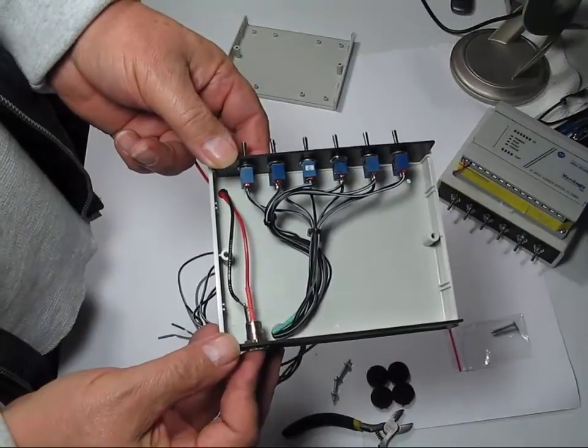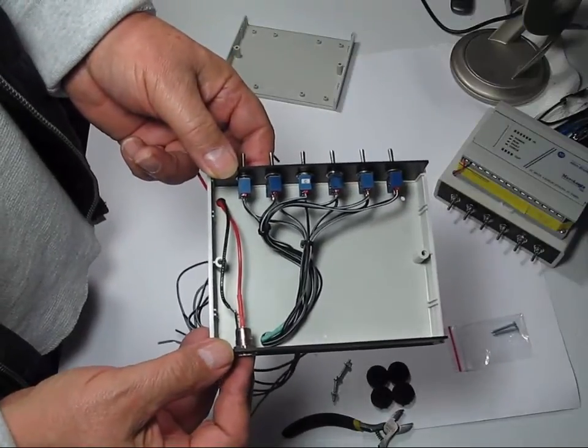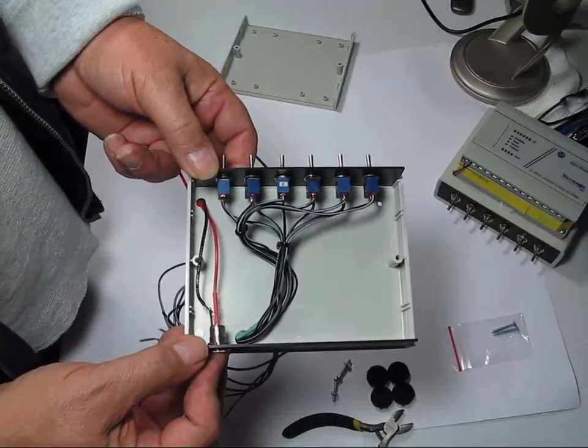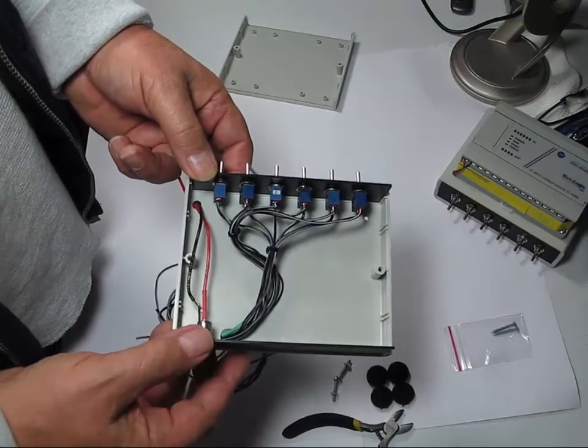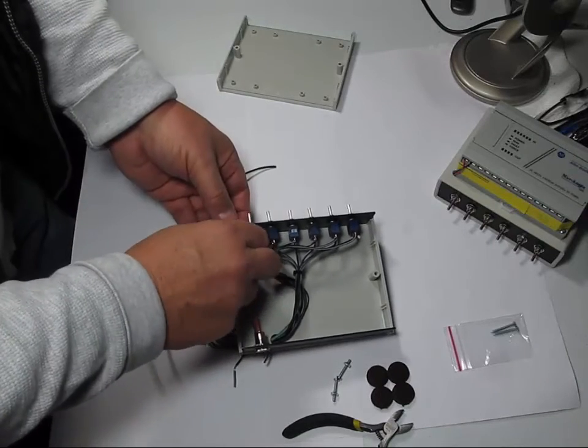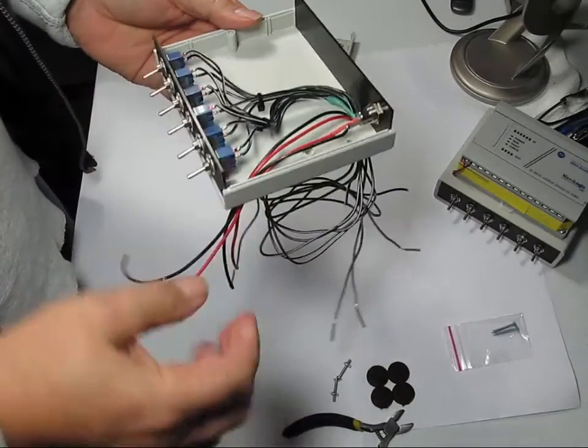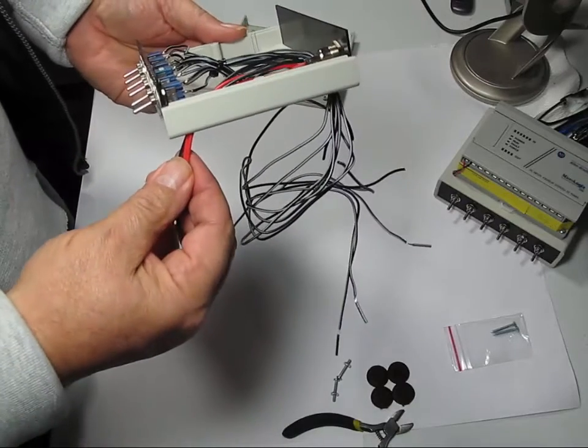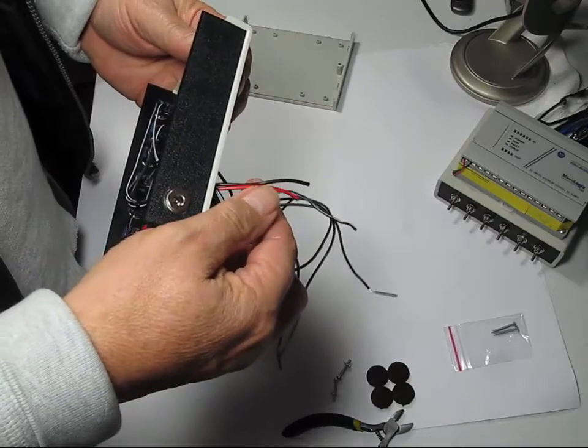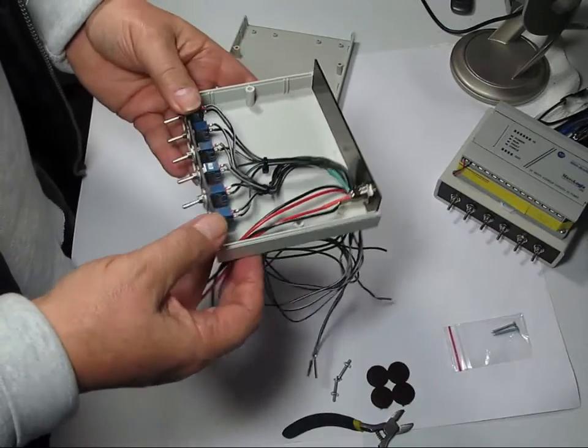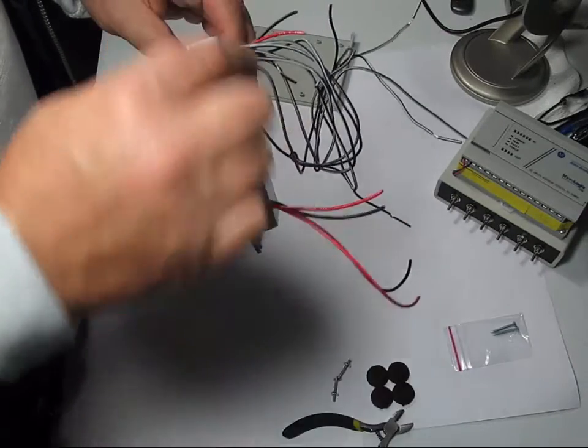Now we have to add a couple more red and black wires to carry the 24 volts DC from the DC input terminals on the controller to the back side to the input terminal strip to power the inputs. So we'll take two more conductors and we'll place them. You see now we have a red and black that we've added going from this front corner back to the back corner that's going to be for the inputs. And we can tie wrap those now.